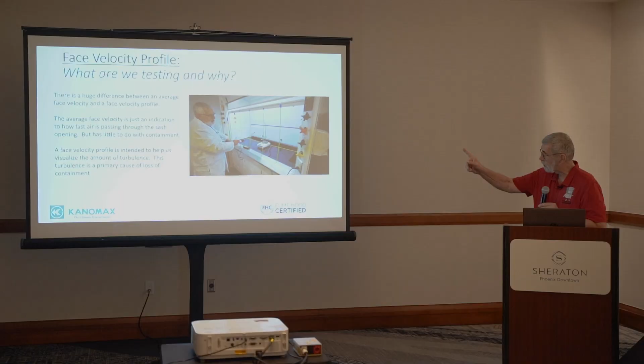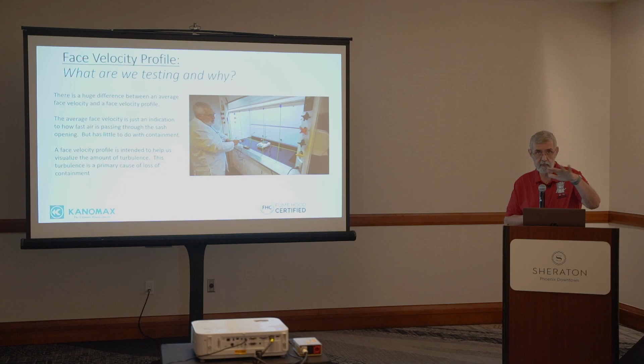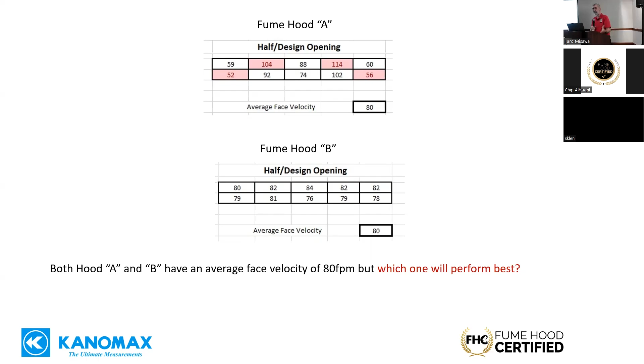So what face velocity profile does is it helps us understand how much turbulence. So the more difference there is in the numbers, the more turbulence there is. The more the numbers are similar, the more laminar it is and less turbulence. So let's look at these two hoods. So here's hood A. Hood A, it's got a low of 52 and a high of 114. And you can see some red or pink cells and some white ones. But it's got an average face velocity of 80. Now here we have hood B, and it has the numbers you see there, and it has an average face velocity of 80. Now, what does that really mean?